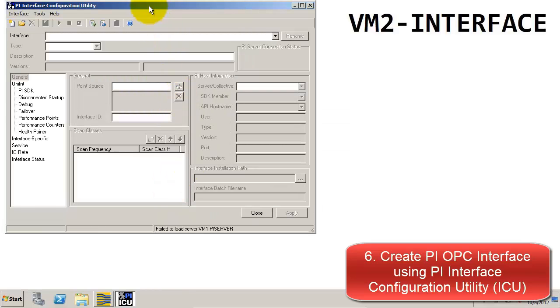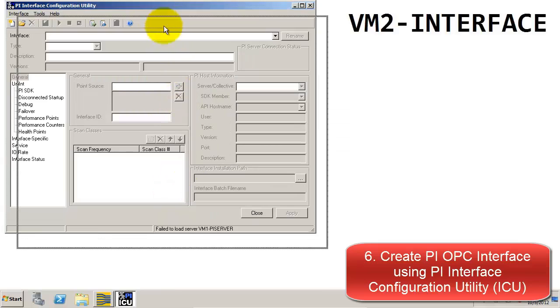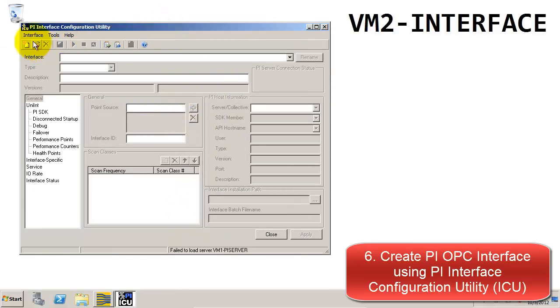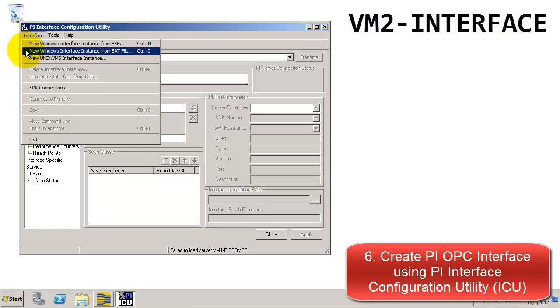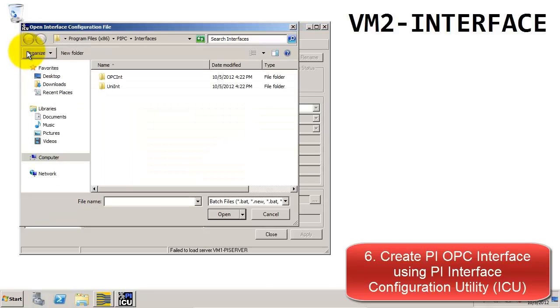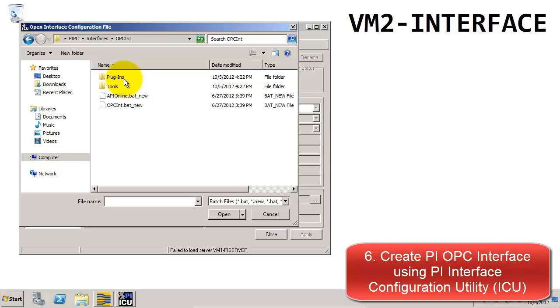Now that we have the ICU open, we're going to create our OPC interface. Go to the Interface tab at the top and select New Windows Interface Instance. For our case, we're going to choose From the Batch File. Then we're going to open the OPCINT folder, and from there select opcint.bat_new.